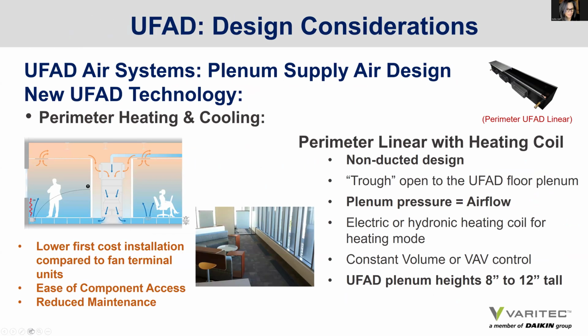Perimeter heating is different. Instead of using fan terminal units, linear troughs are now provided along the perimeter with either electric or hydronic heating devices in them to wash the perimeter walls with warm air in heating mode or cool air in cooling mode. And this takes the place of the fan terminal unit that was used in the older technologies.